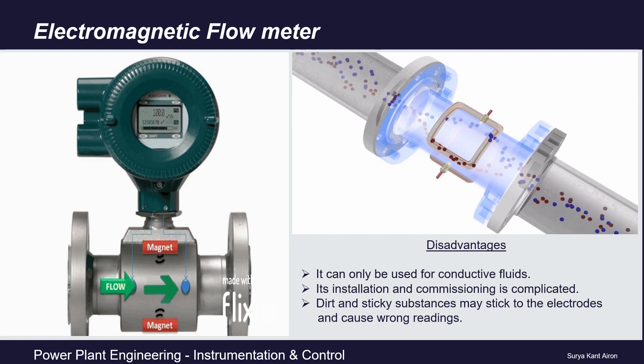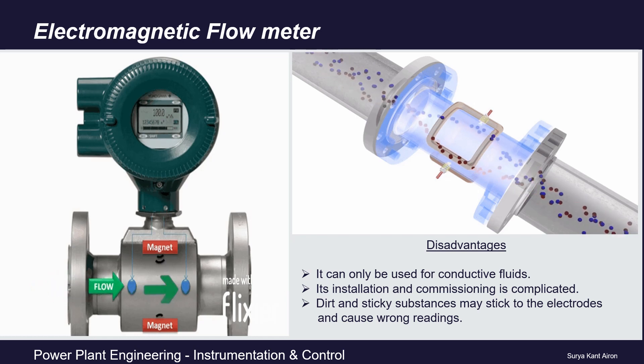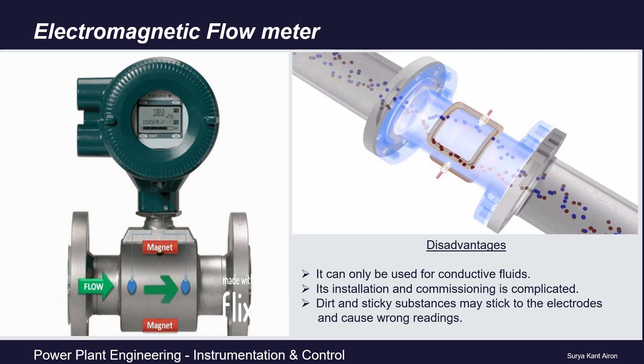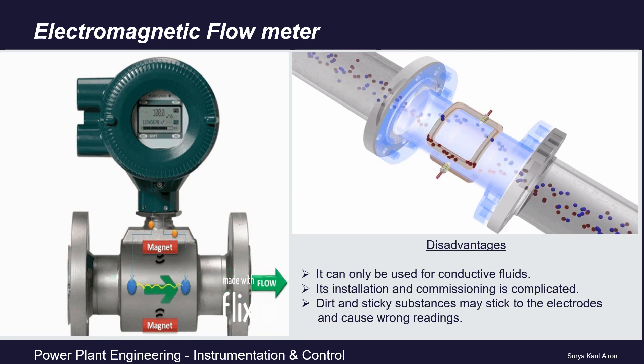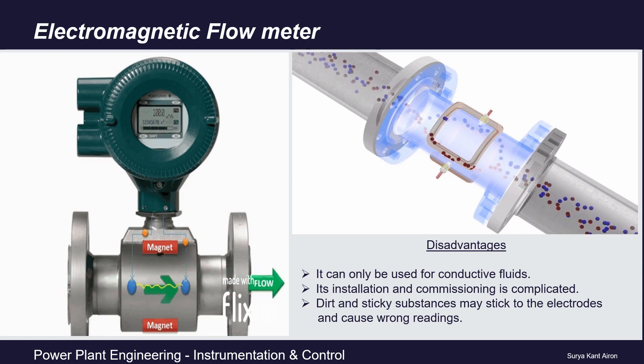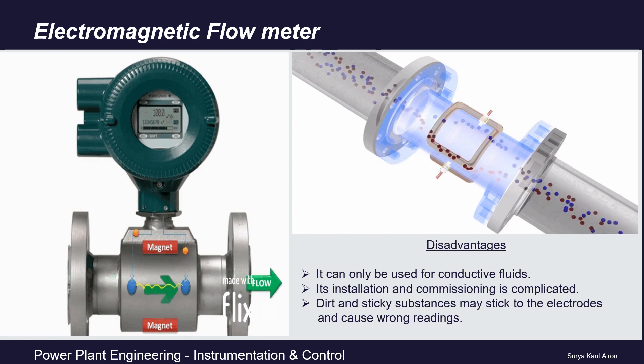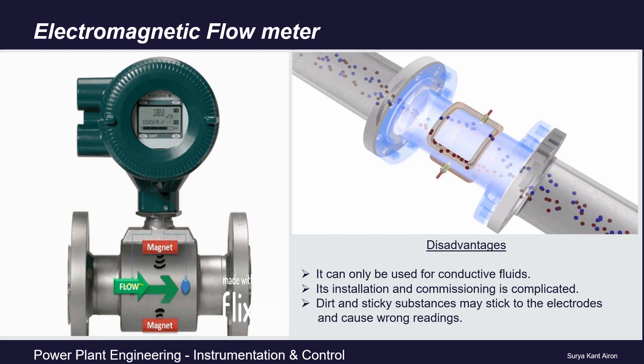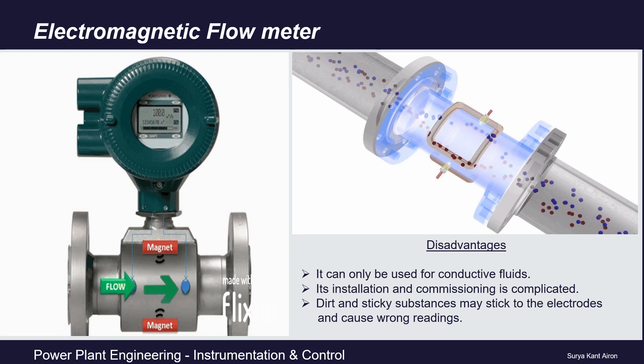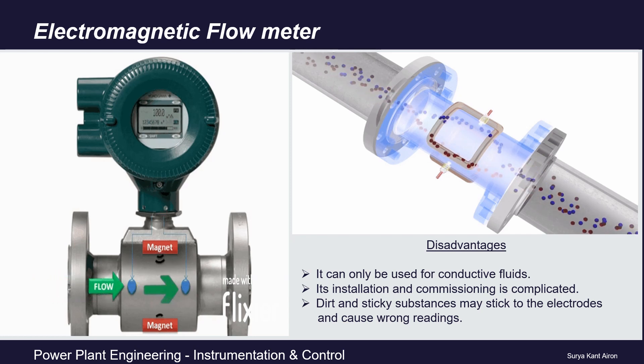This transmitter is calibrated to give a 4 to 20 milliampere signal corresponding to the voltage generated. This 4 to 20 mA is transmitted to DCS or PLC to show the volumetric flow. The voltage generated is directly proportional to the velocity of the positive and negative ions in the fluid, so voltage is proportional to fluid velocity, and velocity is directly proportional to flow rate. Therefore, voltage generated is directly proportional to fluid flow rate. This measured flow is volumetric flow and is affected by pressure and temperature variations.